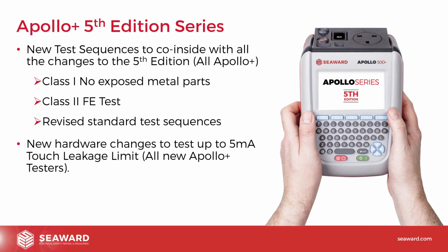Obviously, the main change as well is we've updated the hardware. So we've done a hardware modification to allow the measurement range of the Apollo to measure all the way up to 5 milliamps for the touch leakage. That has to be a hardware change. It won't measure otherwise. It previously only had to measure up to 0.25.